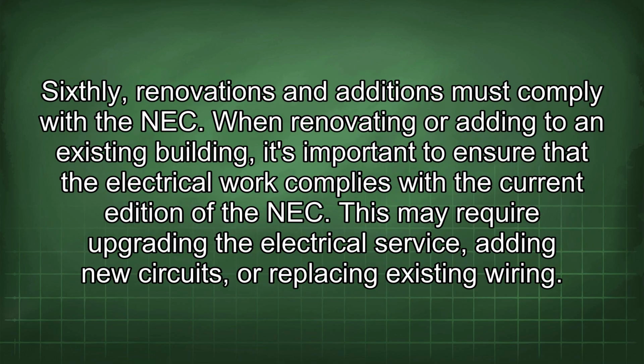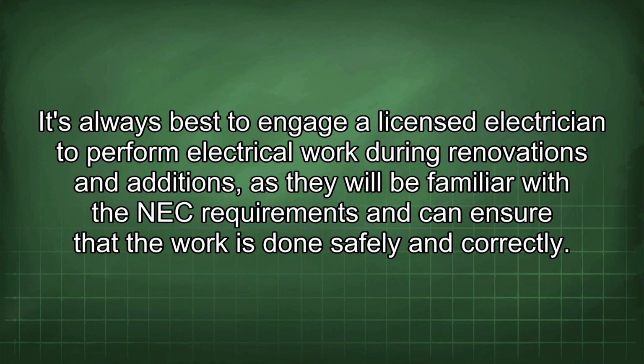Sixthly, renovations and additions must comply with the NEC. When renovating or adding to an existing building, it's important to ensure that the electrical work complies with the current edition of the NEC. This may require upgrading the electrical service, adding new circuits, or replacing existing wiring. It's always best to engage a licensed electrician to perform electrical work during renovations and additions, as they will be familiar with the NEC requirements and can ensure that the work is done safely and correctly.